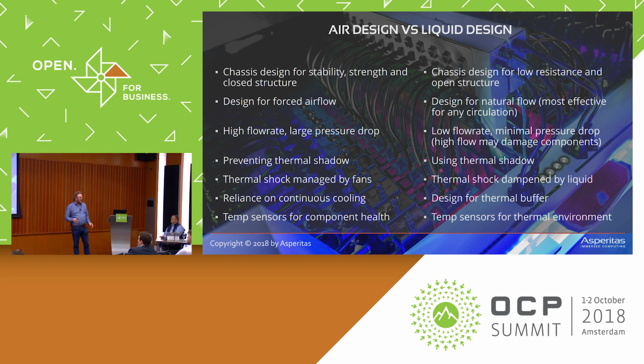Thermal shock is something most of you deal with in air-cooled systems, where high temperature fluctuations influence materials, causing them to expand and shrink. Over time that may be one of the causes for a long-term defect. Within liquid, that is fundamentally different, so you can apply different types of standards to component-level design.